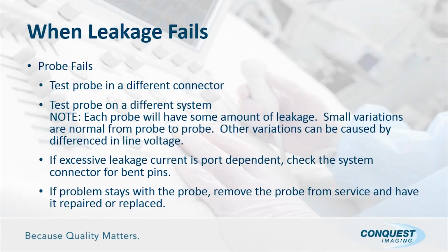Well, what about when a probe fails? One of the first things you can do is test it in a different connector to see if it's a problem with the probe or maybe a connector in the system itself. If there's no change when you do that, and you have another system, test it on a different system. It makes it real easy. It says each probe will have some amount of leakage, normally very small, and small variations are normal from probe to probe. So even if you have two identical probes, it doesn't mean they're going to leak at exactly the same value. It goes on to say that any variations in line voltage can cause different amounts of leakage, so going to a different system in a different room can cause a variation also.